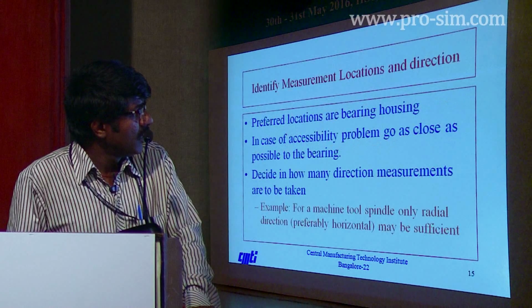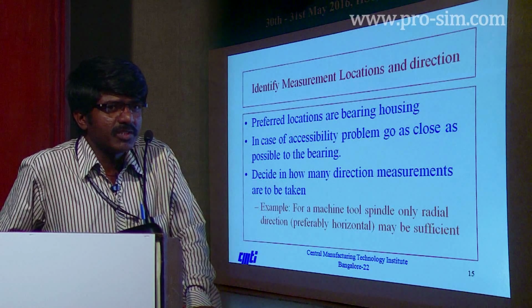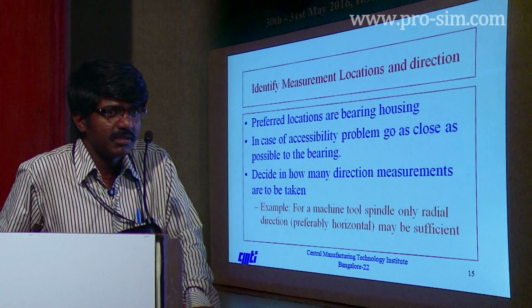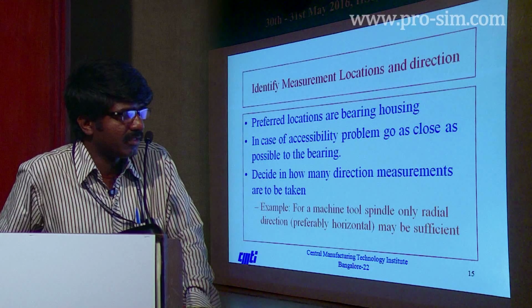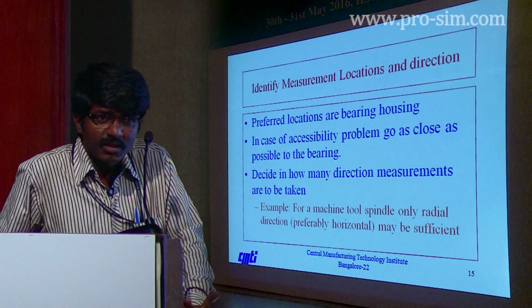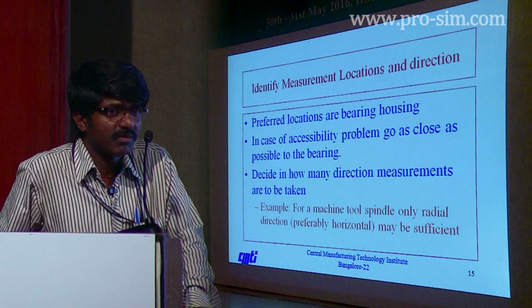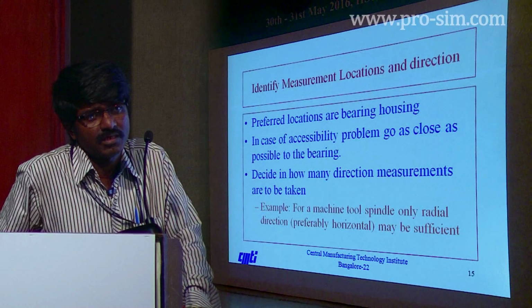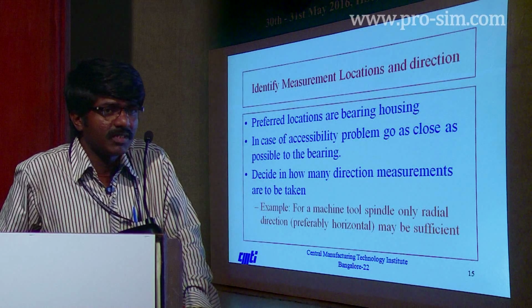Next is where to measure. We have selected the machine. The next thing is where to collect the vibration data. The preferred locations are the bearing housings, because whatever reactions are there will act on the supports. The supports are nothing but the bearings.